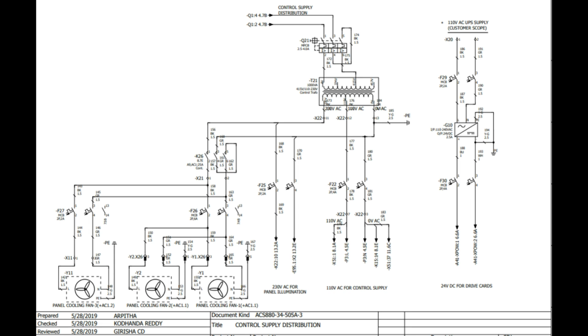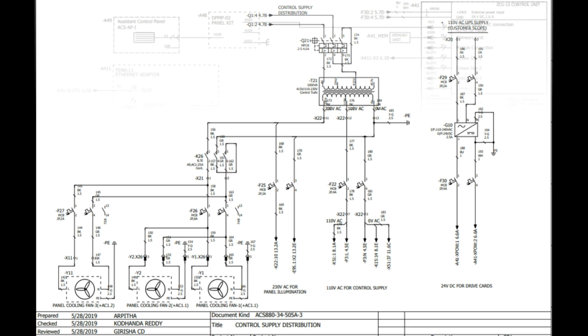Here you can see on the left hand side there are three panel cooling fans, and for drives, panel cooling is very critical. It is more important than, you can say, DOL or RDOL or any other starters, because for drives, taking out the heat generated in the drive is very critical. The temperature can go up to 50 and 55 degrees Celsius. So cooling fans are very critical in drives. If we don't have a cooling fan, the drive will continuously trip on over temperature fault.